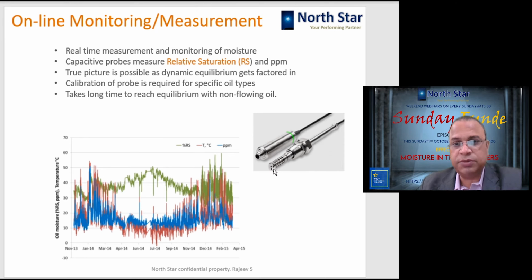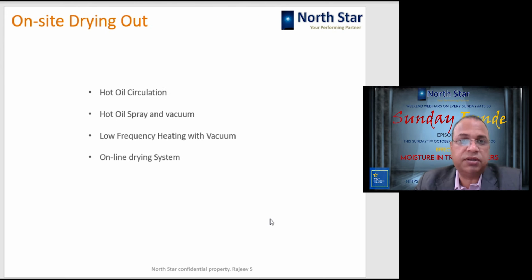Based on this, you can see here, this probe is continuously there, and it is going to monitor the moisture inside the oil continuously. Here it is percentage relative saturation, ppm, and temperature. These are three different graphs which you can easily study anytime to understand what is what in my transformer. Relative saturation is the term to keep in attention when you are trying to take decisions based on your oil testing and oil analysis approaches.